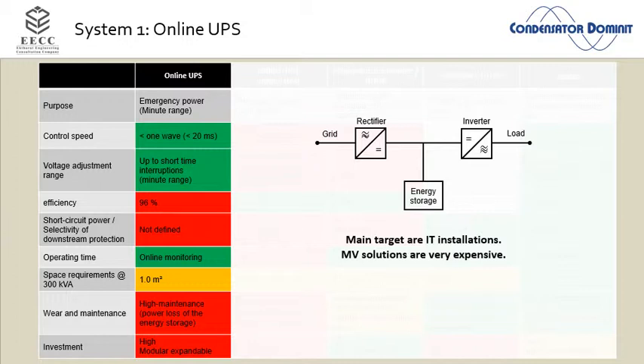It works very well if I can identify my most important processes, where I say the process controller goes behind a UPS, the IT department goes behind a UPS. But don't ask me to start a large motor behind a UPS. Don't ask me to run a distributed grid behind a UPS. It is very challenging, it's very expensive, you lose the selectivity, and you reduce your grid's short circuit power drastically.